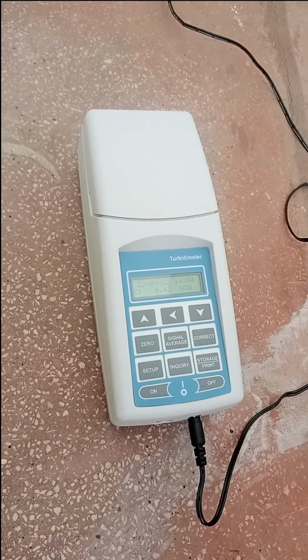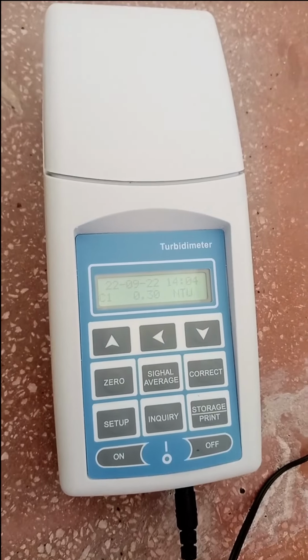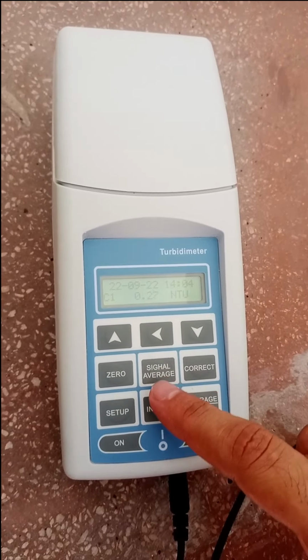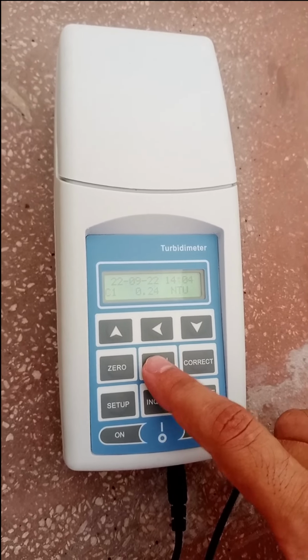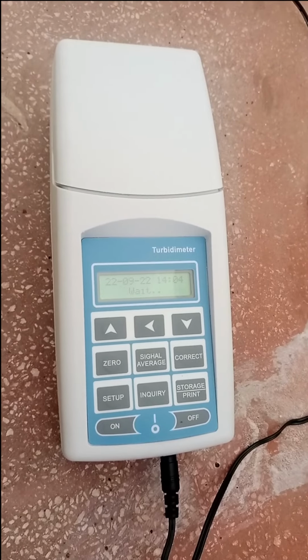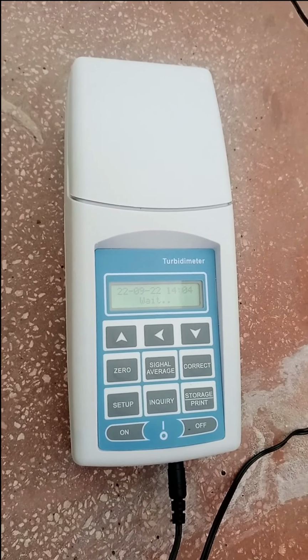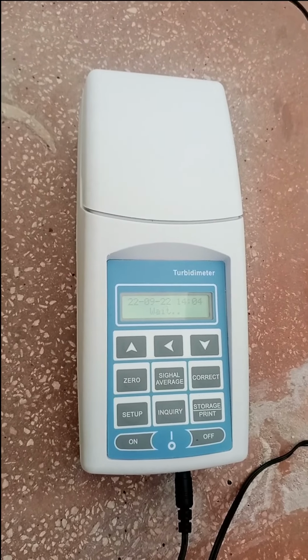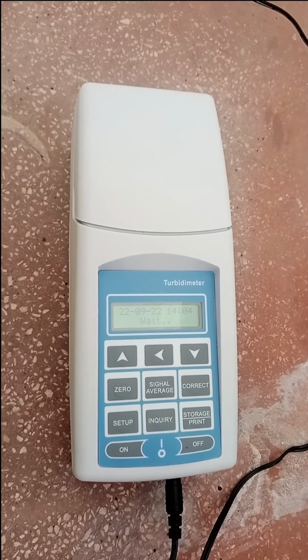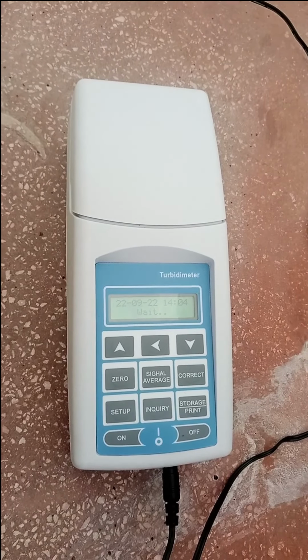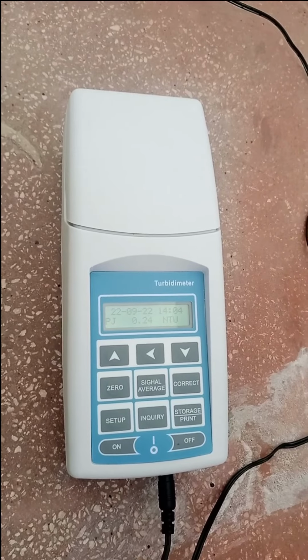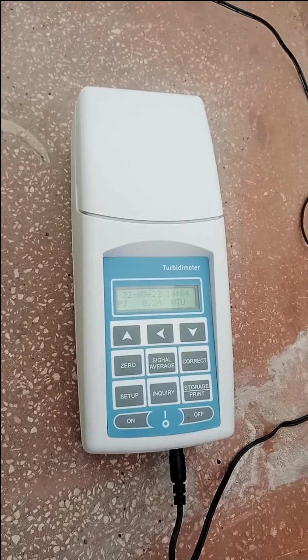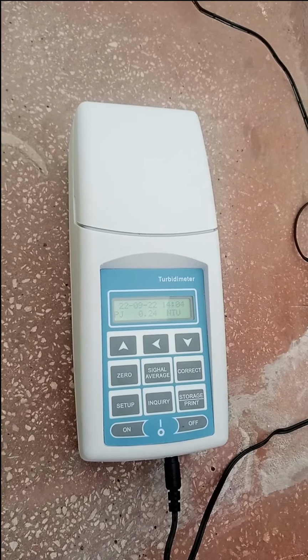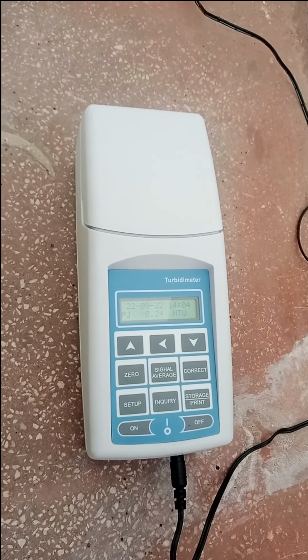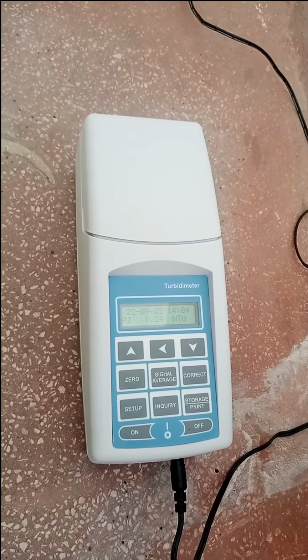Now it will give you a value. When it's stabilized to a value and you want to reconfirm it with an average value, press the signal average button and wait for at least 10 to 15 seconds. It will spread the signals in at least 5 to 6 directions and give you the average value of the different signals. Right now it is processing. You are supposed to wait for at least 10 to 15 seconds. Now you can see that the value came down from 0.32 to 0.24, because that is the average value. If we take the value of tap water or tube well water, it is around 0.2.